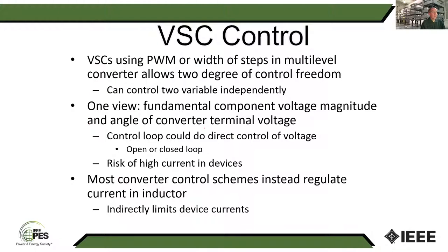And so when we talk about the controls for this, generally whether they're choosing pulse width modulation or using the control for a modular multi-level converter, you have basically two variables that you can control independently. You might think of that as P and Q. You might think of it as voltage magnitude or current angle. So there are a number of ways you can view that. And then we'll talk about frequency control in a second. One way you can view this is you could do a direct control of voltage, open loop or closed loop. We'll talk about applications where you want to do direct control of voltage in a couple of minutes.